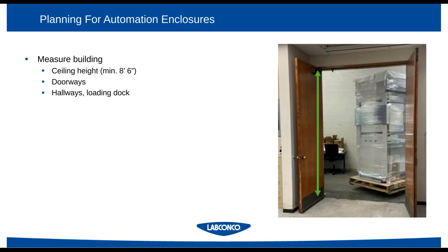Additionally, as you get these units into facilities, as Simon mentioned earlier, it's really important for you to consider the dimensional requirements for the doorways, for the loading dock, and other locations where you'll be receiving instrumentation. So with the Logic View, the installation minimum requirement is 8 foot 6 inches. So it's often safe to say that an 8.5 foot ceiling will be compatible. More is obviously better if available.